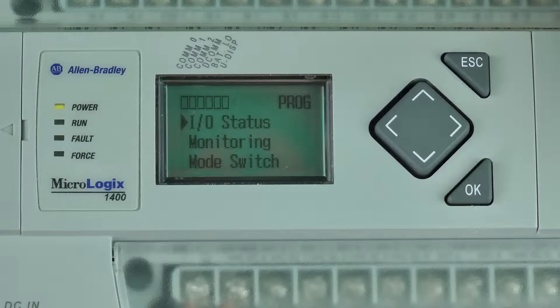Most MicroLogix controllers have a DCOM mode which allows you to toggle between your application's custom settings for COM0 and the default settings for COM0. This can be very helpful when you've set COM0 to be something like Modbus, but you need to use that same port, COM0, to download a program using DF1.